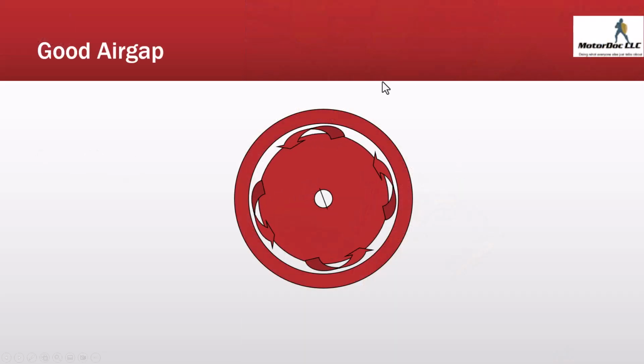So if I have a perfect voltage coming in, I'll have a perfect current going out. If I have the rotor off to one side and I have that unbalanced magnetic pull, I have to consider the inverse square law of fields, in which the pull is many, many times larger on one side, and many times lower on the other, so it stands out. It might only be a few thousandths of an inch, but it definitely will appear in the field, and the magnetic field has a direct relationship to current.